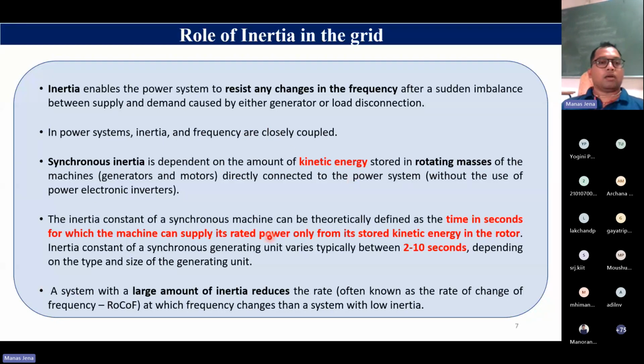So a system with a large amount of inertia reduces the rate at which the frequency changes following the contingency, the so-called ROCOF, rate of change of frequency, right. And typically we express the inertia in seconds, typically varying from 2 to 10 seconds or so. So what is the physical interpretation of it? It is the time in seconds for which the machine can supply its rated power only from its stored kinetic energy. This is what we refer to as the inertial response following a contingency, right. So this is the role of inertia in the grid.